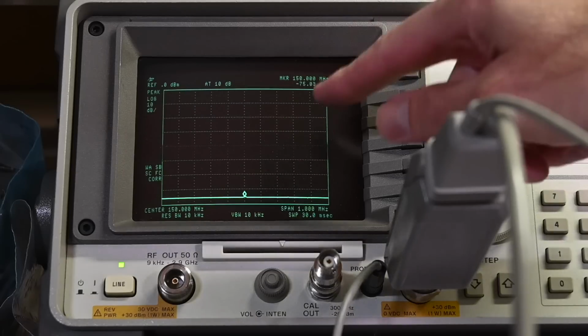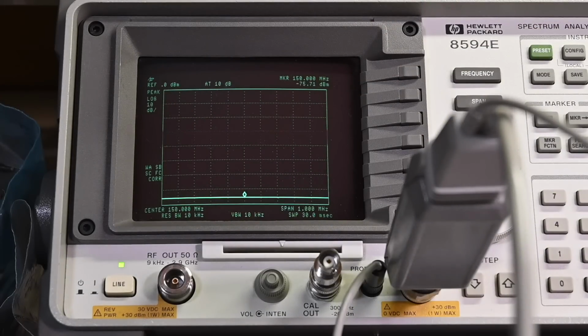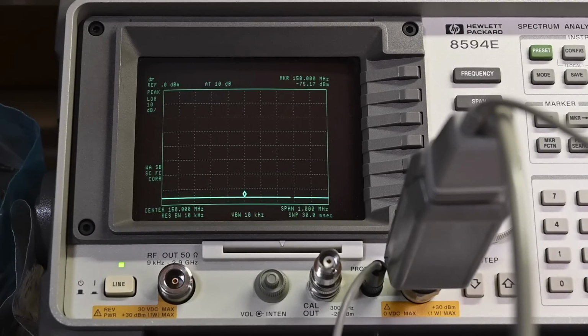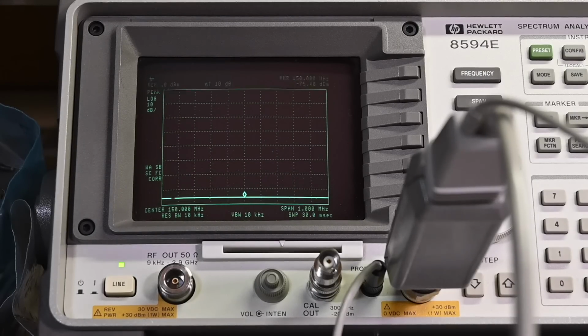So the reading that you see up here is exactly the reading that the probe is making. There's no attenuation factor. You have to be very careful with this probe because the damage level with no attenuation on the end is just 1.5 volts peak. So very sensitive. Static electricity can also damage these probes.